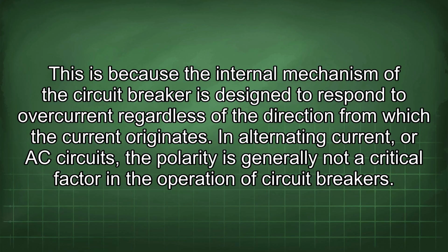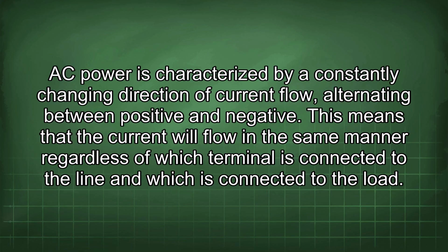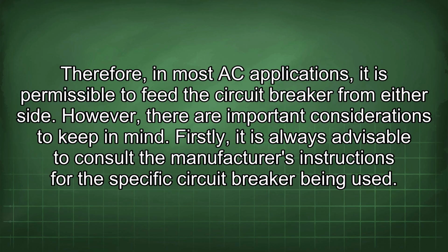In alternating current, or AC circuits, the polarity is generally not a critical factor in the operation of circuit breakers. AC power is characterized by a constantly changing direction of current flow, alternating between positive and negative. This means that the current will flow in the same manner regardless of which terminal is connected to the line and which is connected to the load. Therefore, in most AC applications, it is permissible to feed the circuit breaker from either side.